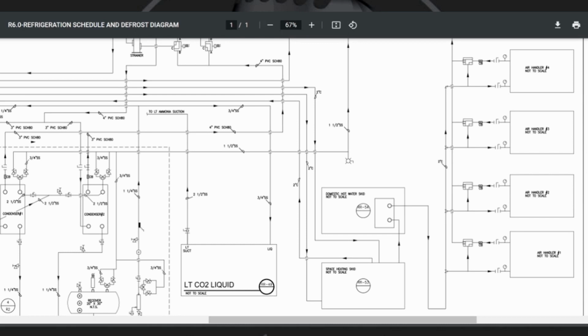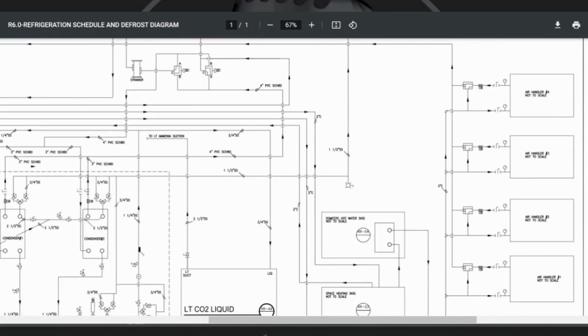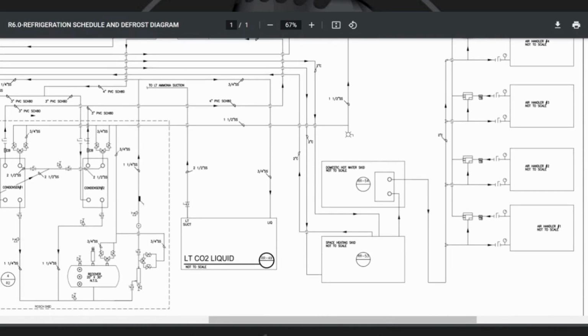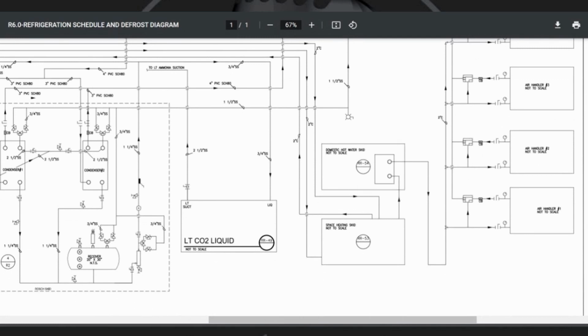I'm not seeing it here. Is that not on this print? It is basically not on that print. Oh, okay. So basically you're using the medium temp liquid overfeed of the CO2 to chill down the heat exchangers, which chill down the glycol, which end up running to these same air handlers because basically you're doing heating and cooling. Is that correct?